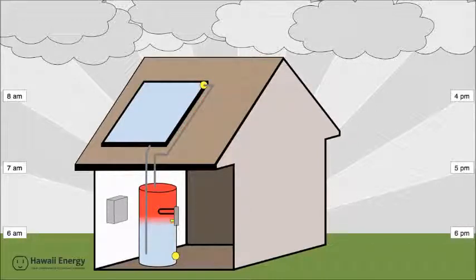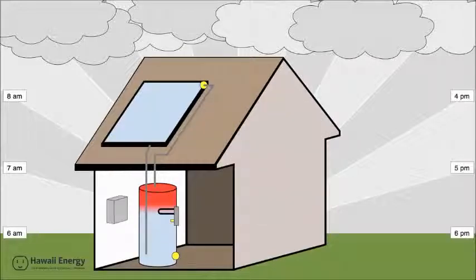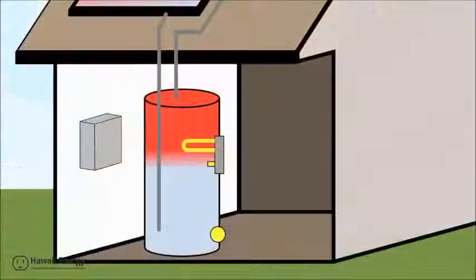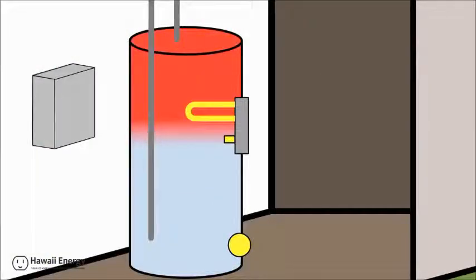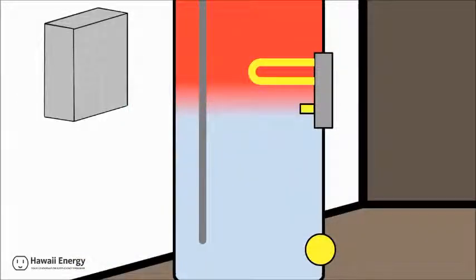As a result, the water temperature in the tank will fall until it reaches the setting of the thermostat, located on the tank. Once the temperature of the water falls below the thermostat setting, usually about 120 degrees, the electric backup heating element is energized and heats the water until it exceeds the thermostat setting. Until the sun returns, your system will rely on the electric backup heating element, but here in Hawaii, this should only be the case around 10% of the year, if your electric backup timer is set correctly and maintained. If the timer is not set correctly, it could cost you a lot of money by unnecessarily heating water. Why? We'll take a look at that in our next video.